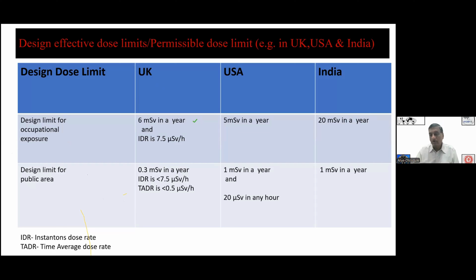You can see the thickness of the primary barrier, and it's not just a planning concern; every year you have to check the radiation leakage outside around the room for safety. Then the secondary barriers, and there are permissible dose limits, which are country specific. So you have to follow the country you are in and the design limit for occupational radiation exposure. For the public there are also limits, the instantaneous radiation dose levels and the time-averaged dose rate. So I just give you that.